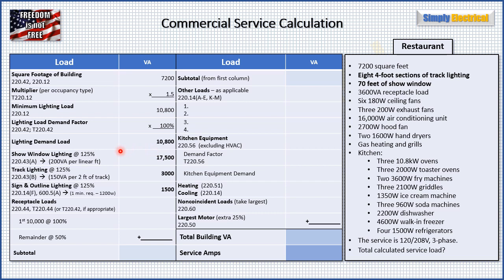Moving on to show window lighting: per 220.43A, we take show window lighting at 200 VA per linear foot. We have 70 feet of show window, so 200 times 70 gives us 14,000 VA. But we have to add an extra 25% because it is a continuous load, meaning it operates more than three hours at a time. That extra 25% takes us to 17,500 VA.